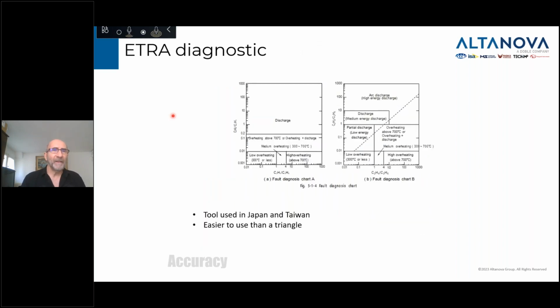Another one being used, and this is very specific, is what we call the ETRA diagnostic. This tool was developed in Japan, and it's mostly used by Japanese customers and OEMs, and also in Taiwan, because the OEMs in Taiwan have a very strong historical connection to the OEMs in Japan. It's a little bit the same as the Rogers ratio: you use a different type of gas ratio, and depending on where it fits, you get your diagnostic. It's much easier to use than the triangle to a certain point, but that diagnostic system has never really been used outside Japan and Taiwan.